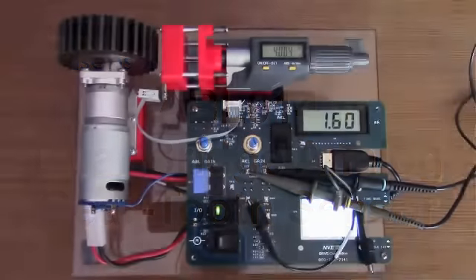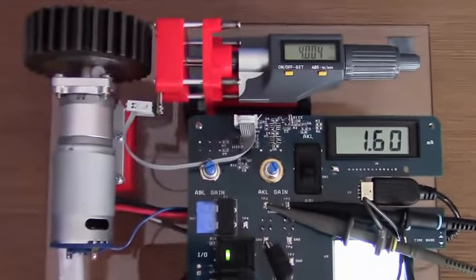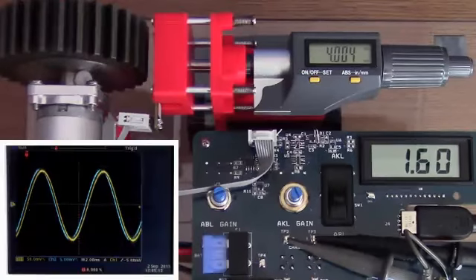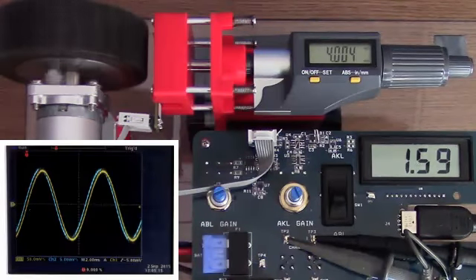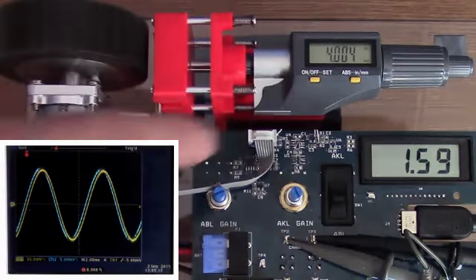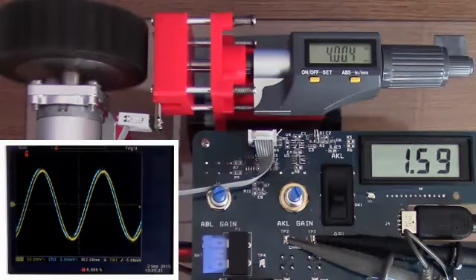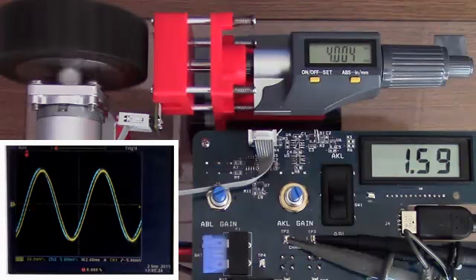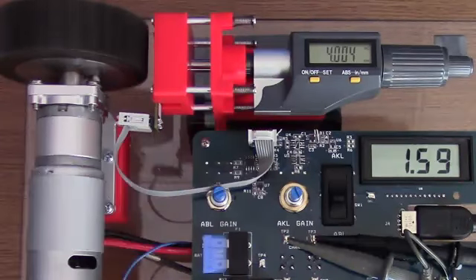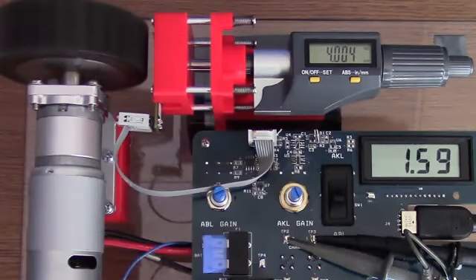Now we have an ABL-014 dual bridge analog sensor and two channels on the scope. The sensor is positioned approximately four millimeters away from the gear tooth. The dual bridge sensor has phase shifted outputs providing direction information. Sensor current is typically two milliamps maximum of 2.5 milliamps. Current is shown on the meter here.